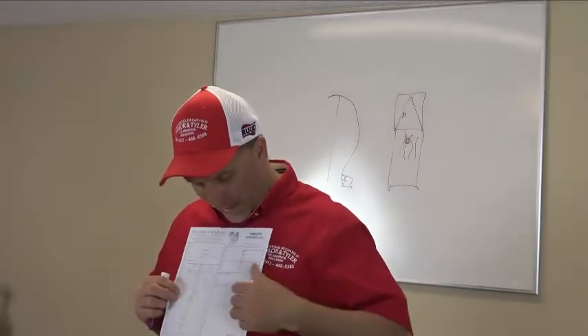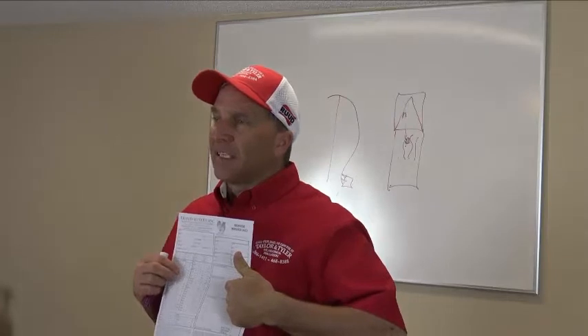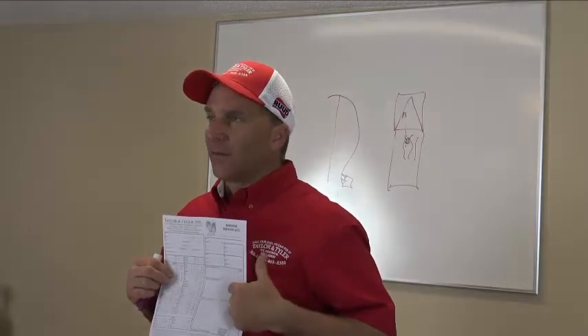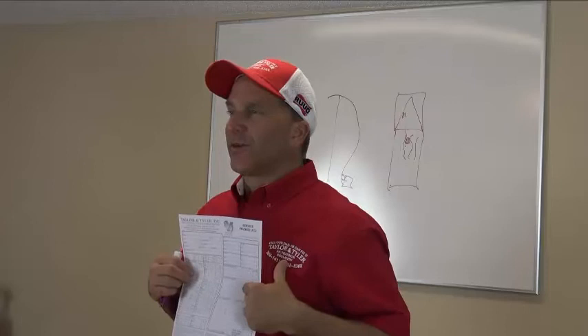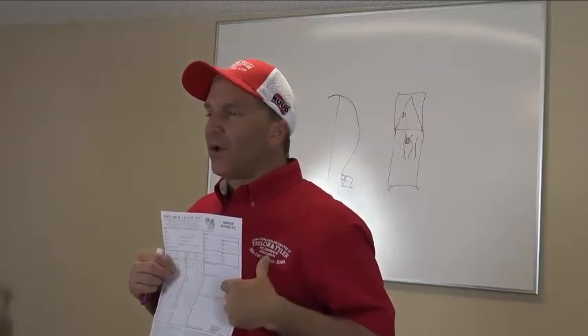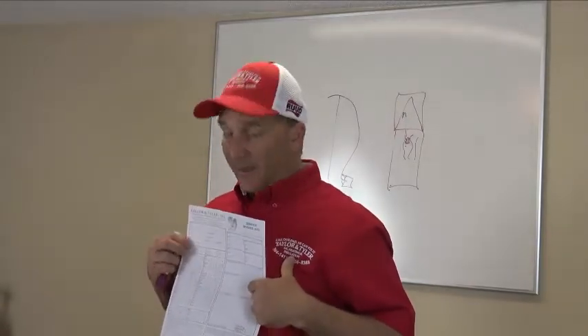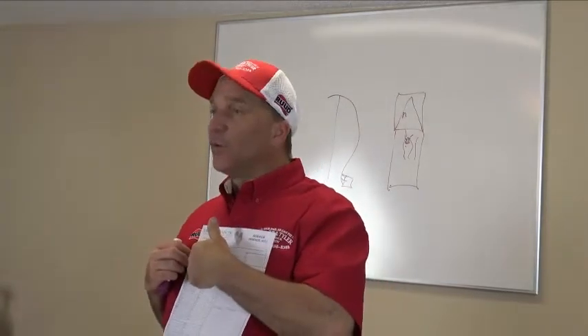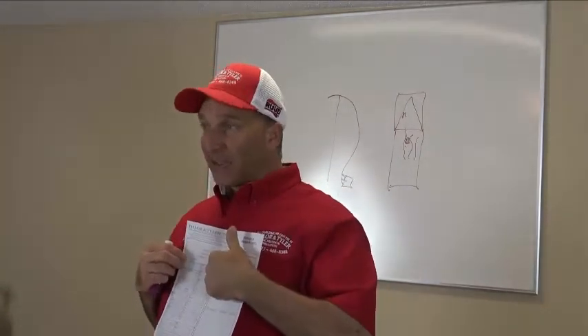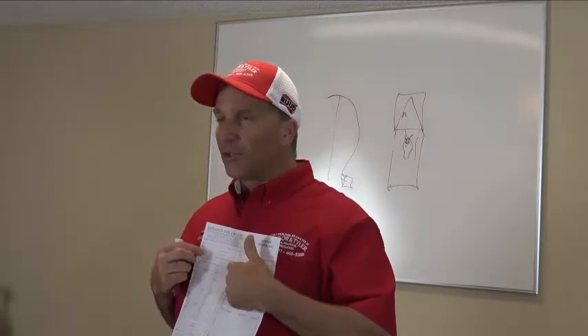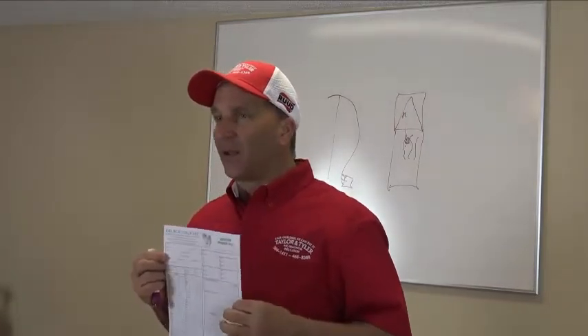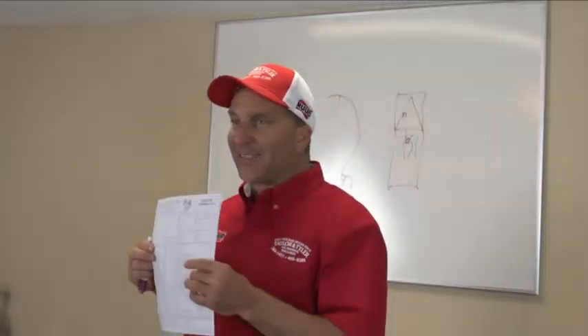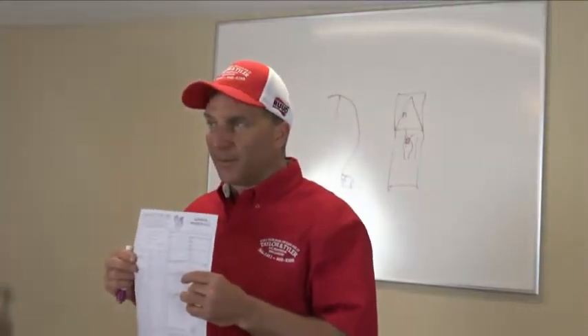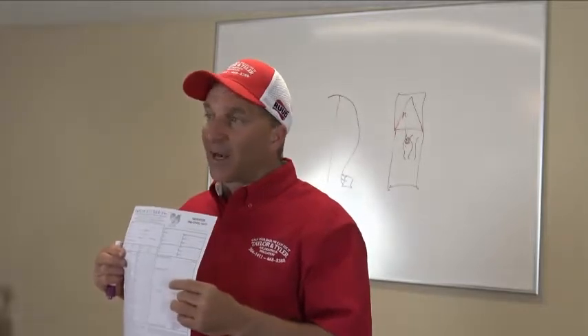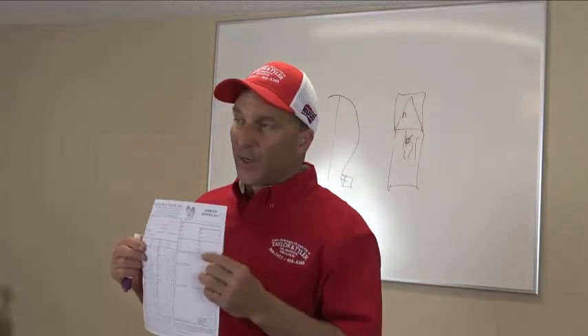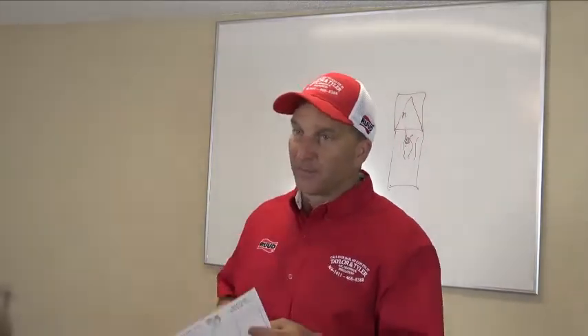You know what you're going to do in this column, in this area right here? System running 4 degree subcooling. Added 2 pounds of refrigerant, whatever it is, brought subcooling to 12 degrees. That should show up here as well, which you're going to have when you got there and when you left. But you should have something on there stating why you added a little bit of refrigerant and is it undetectable and not visible. Okay? Because if you added a lot of refrigerant into this system, then you need a price on a leak search.